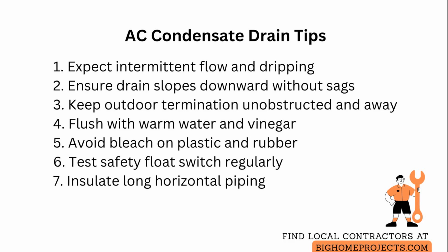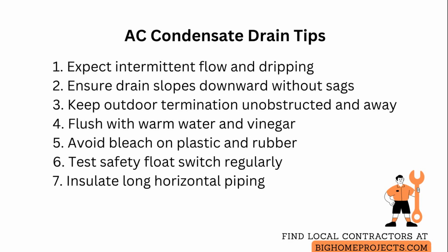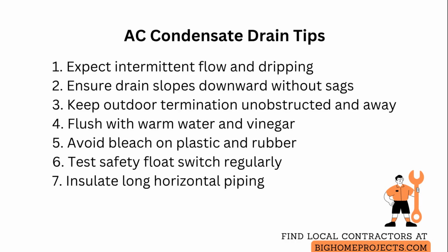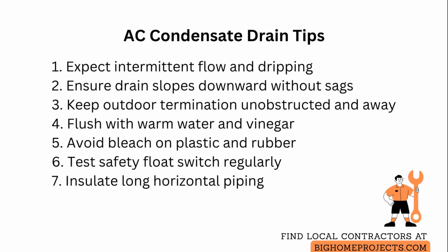Check that the drain line slopes downward from the unit without sags or traps, and that the outdoor termination is unobstructed and positioned to discharge away from the building envelope to avoid pooling near the foundation.